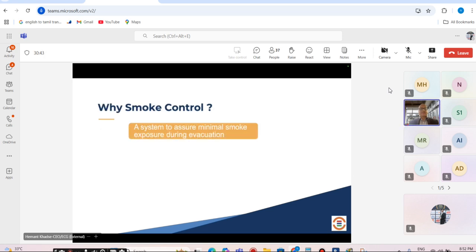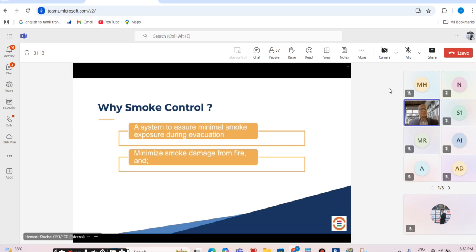So smoke control has a very, very direct impact on evacuation. Why? Because when you activate the smoke management or smoke control systems, it is essentially helping people to evacuate the building safely and speedily. Because we all know that smoke is going to be hazardous for human life, and that's the job. The critical job of a smoke control system is to minimize the smoke damage.